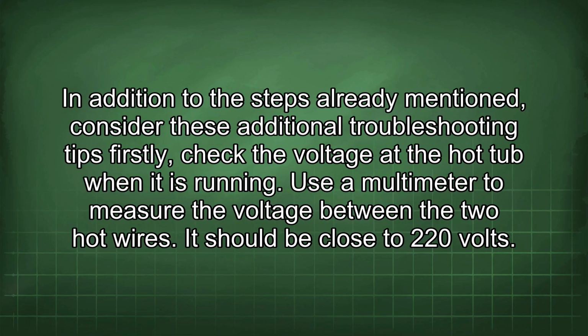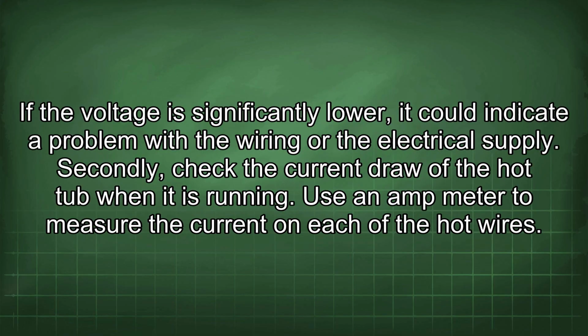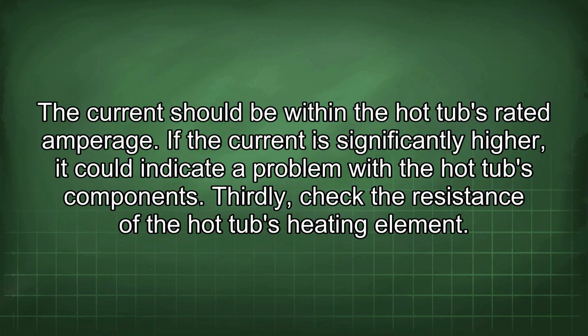In addition to the steps already mentioned, consider these additional troubleshooting tips. Firstly, check the voltage at the hot tub when it is running. Use a multimeter to measure the voltage between the two hot wires. It should be close to 220 volts. If the voltage is significantly lower, it could indicate a problem with the wiring or the electrical supply. Secondly, check the current draw of the hot tub when it is running. Use an amp meter to measure the current on each of the hot wires. The current should be within the hot tub's rated amperage. If the current is significantly higher, it could indicate a problem with the hot tub's component.